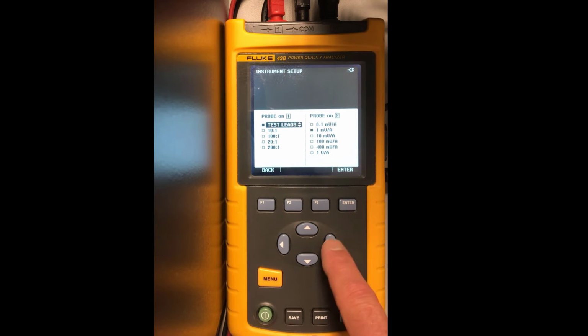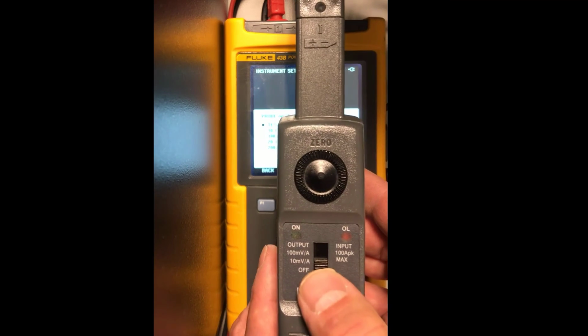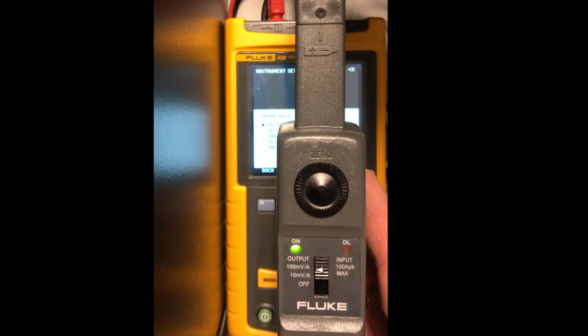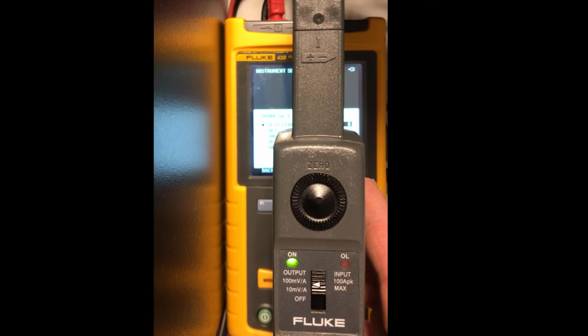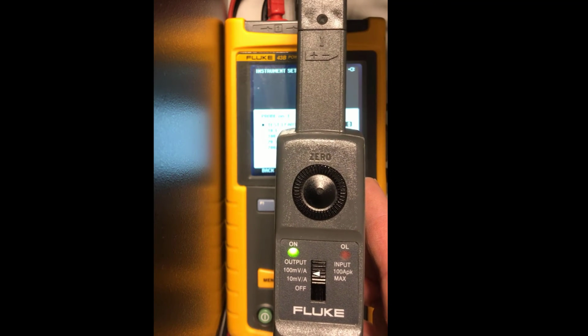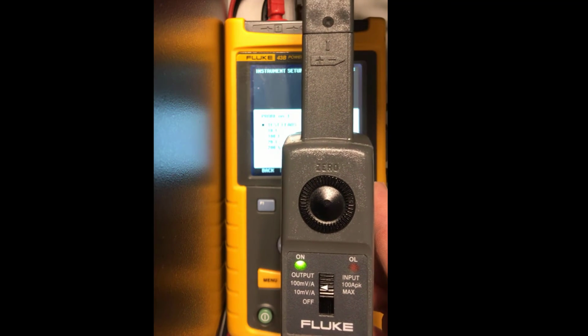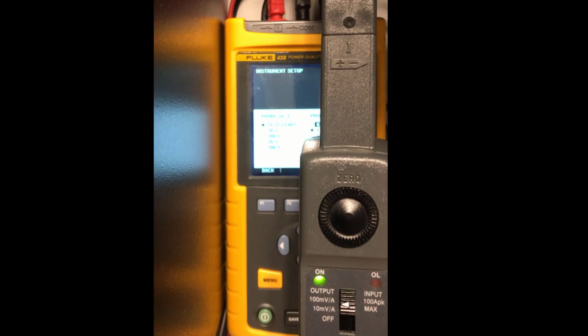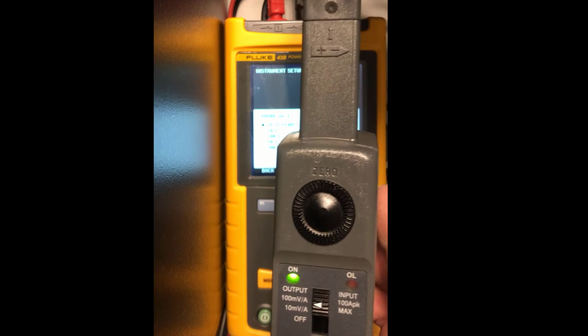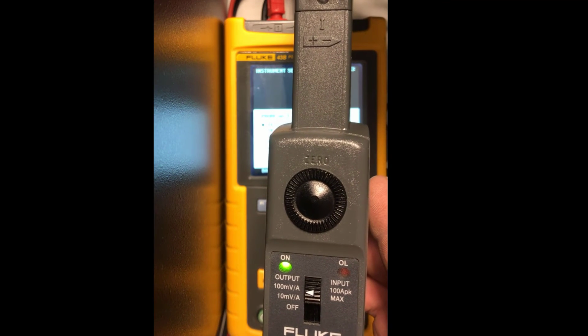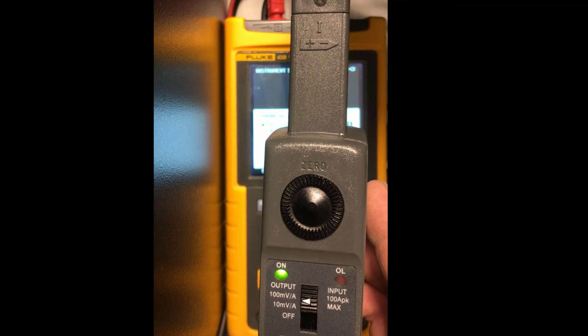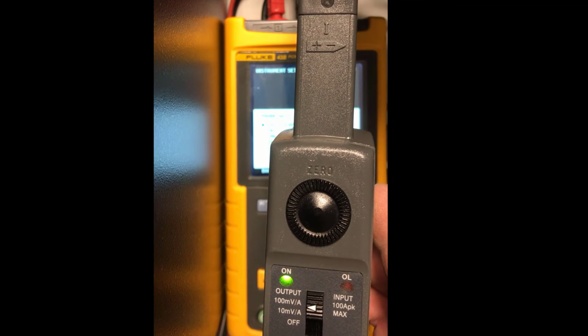And now I use the arrow button to go over to the current probe. Now, the current probe is where it's all relative to the setting on the probe. So this is where you turn on the probe on the top, and what you want to look for is a solid green light. And you can see I have a solid green light here. That's the first step. What I want you to always use by default is to push the switch all the way up to the top and be using the 100 millivolts per amp setting. 100 millivolt per amp setting.